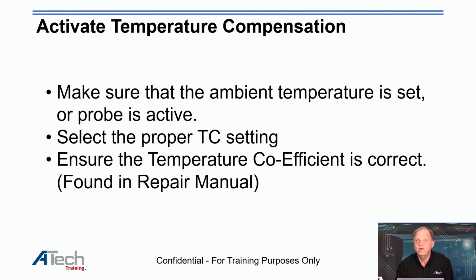One other setting you want to look at is called temperature coefficient. The temperature coefficient is usually found in your manual, but here's the deal. If the windings on this are copper, they're starting to use aluminum for some of the windings. The thermal coefficient is different on those particular metals, so you have to compensate for that. Again, you're using your tool to do that. It makes your life a little bit easier because you've already got compensations for it, so you don't have to add or subtract. The tool's doing it for you.